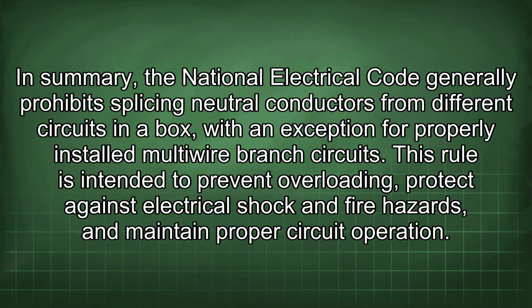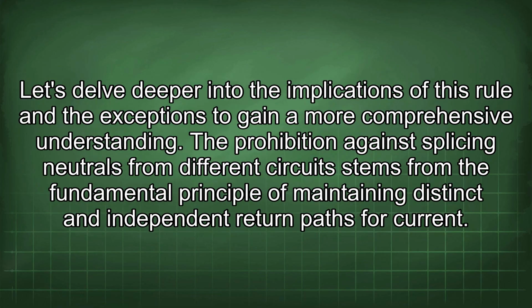In summary, the National Electrical Code generally prohibits splicing neutral conductors from different circuits in a box, with an exception for properly installed multiwire branch circuits. This rule is intended to prevent overloading, protect against electrical shock and fire hazards, and maintain proper circuit operation. Let's delve deeper into the implications of this rule and the exceptions to gain a more comprehensive understanding.